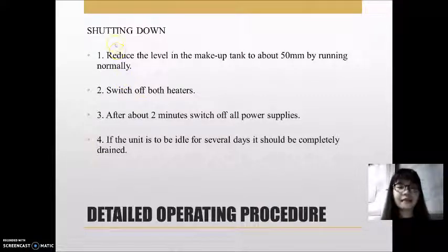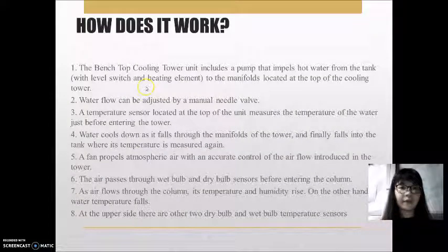And the last operating procedure is shutting down. Reduce the level in the make-up tank to about 50 mm by running normally. Switch off both heaters. After about 2 minutes, switch off all power supplies. If the unit is to be idle for several days, it should be completely drained.